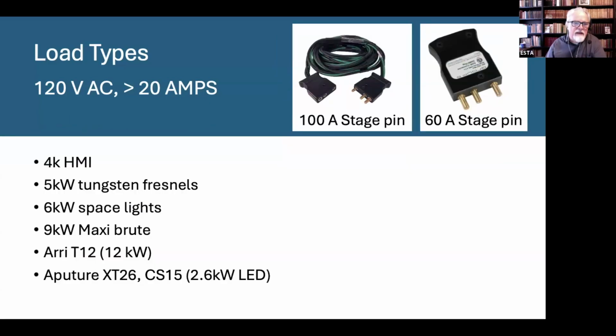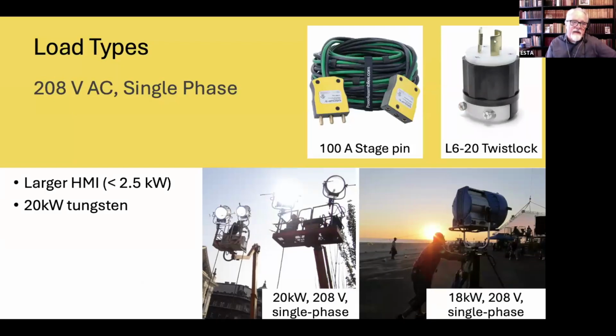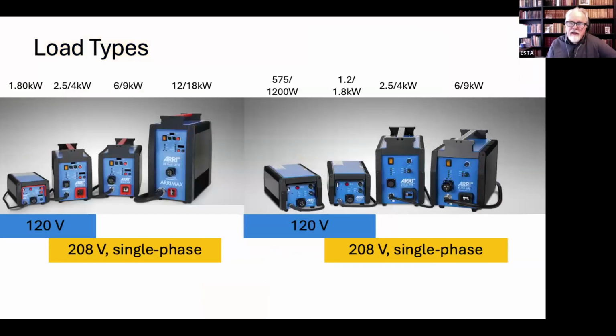The next thing you could end up with is something that's more than 20 amps. Like 4K, 5K, 6K, 9K lights, Arri T12, which could be a 120 volt light that requires a much bigger connector. So you have to accommodate that. Then you've got 208 volt single phase loads, like the larger HMIs, the ArriMax, the 20K tungsten lights, just to give a couple of examples. And a lot of the HMI ballasts are 120 or 208, or they could be both.